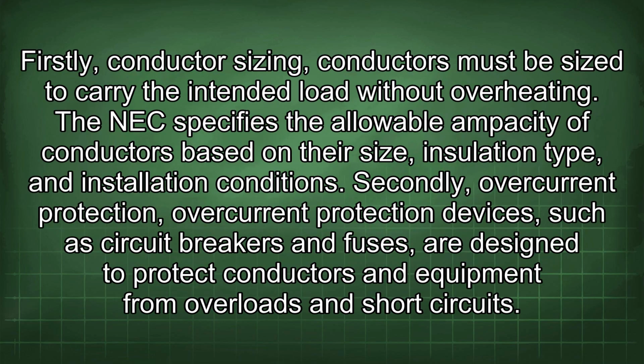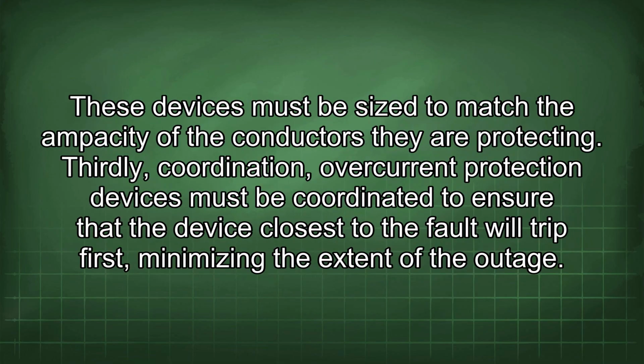Firstly, conductor sizing. Conductors must be sized to carry the intended load without overheating. The NEC specifies the allowable ampacity of conductors based on their size, insulation type, and installation conditions. Secondly, overcurrent protection. Overcurrent protection devices, such as circuit breakers and fuses, are designed to protect conductors and equipment from overloads and short circuits. These devices must be sized to match the ampacity of the conductors they are protecting.